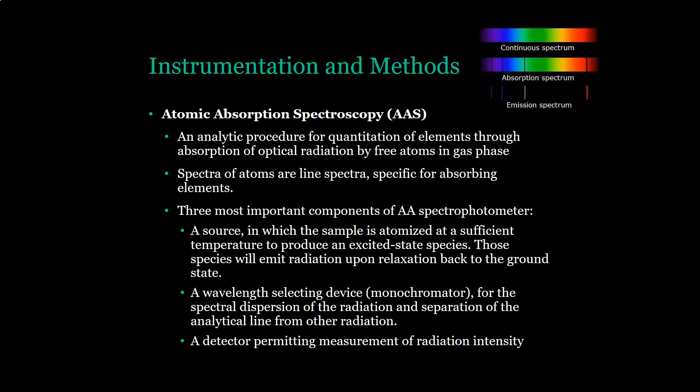The three most important components of the AA spectrophotometer are again: the source, in which the sample is atomized at sufficient temperature to produce an excited-state species, and those species emit radiation upon relaxation back to the ground state; a wavelength-selecting device, also known as a monochromator, for spectral dispersion and separation of the analytical line; and a detector that permits measurement of radiation intensity. AAS and AES are very similar.